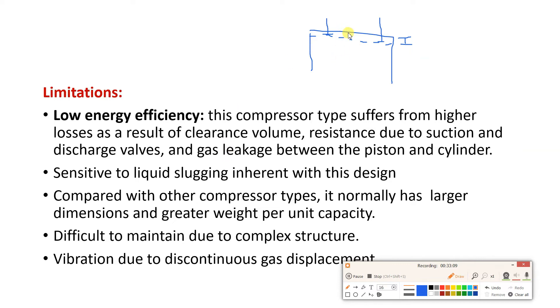Because of clearance volume, some gas — after discharge — expands here. The piston goes from TDC (top dead center) to BDC (bottom dead center). When the piston is at TDC, the clearance volume gas remains and expands when piston moves down, which affects the volumetric efficiency. Because of this, there is an effect on discharge pressure and overall energy efficiency is reduced due to re-expansion loss.